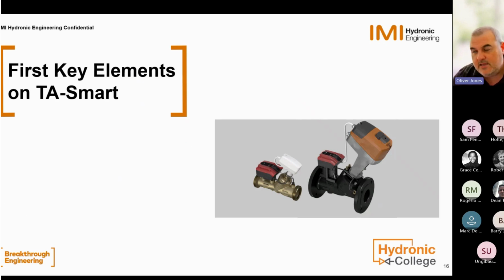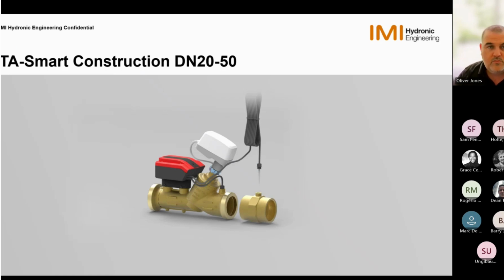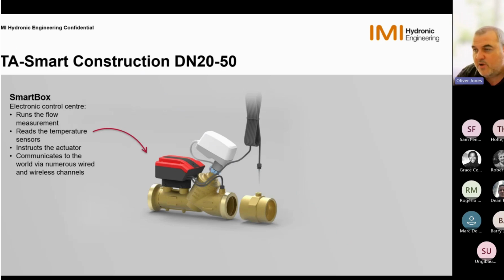So if we take a look at the key elements of the TA Smart. We have our smart valve and the smart box. This is where all of the brain control work is being done. So this runs our flow measurement and reads our temperature sensors. It instructs the actuator on where to position the control valve itself, and all of our communication, all of our input signals, our power supply, Modbus, BACnet, or connectivity that comes into the valve is also wired and works wirelessly through the smart box itself.